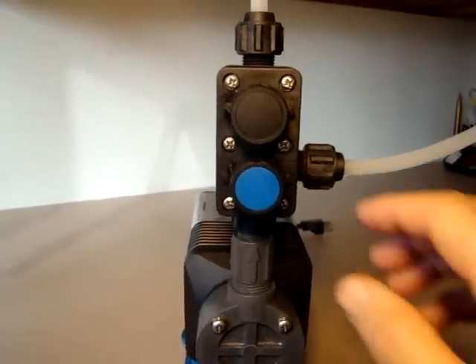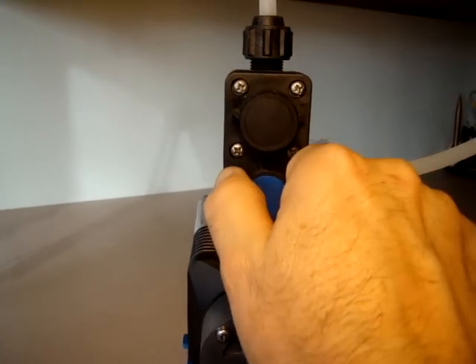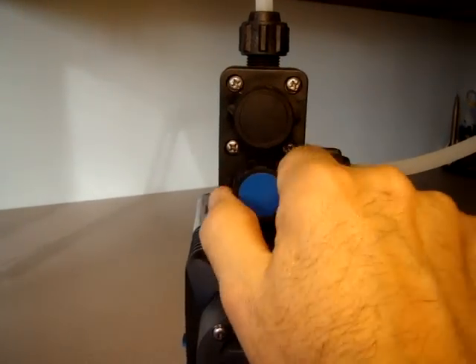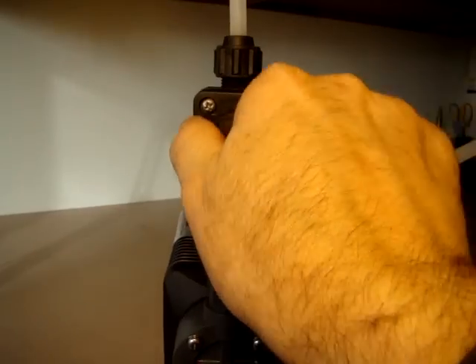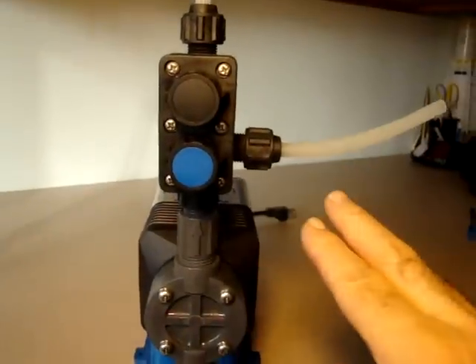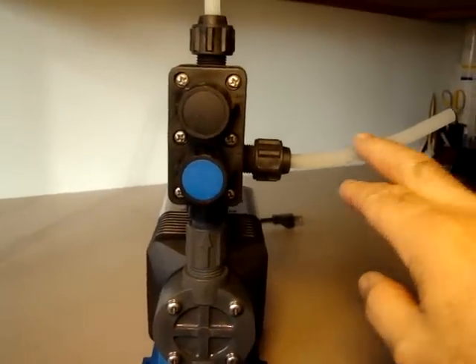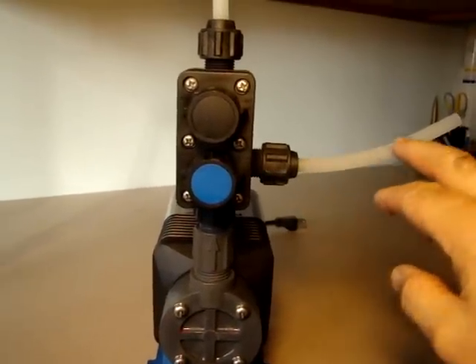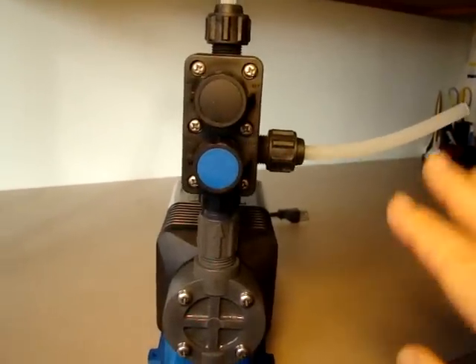To proceed with the air bleed, what you are going to do is turn each knob so that the indicator on the knob is on the right. Then, what you will see while the pump is running, you will see air being discharged along with water out of this line, which will go back in the solution tank.